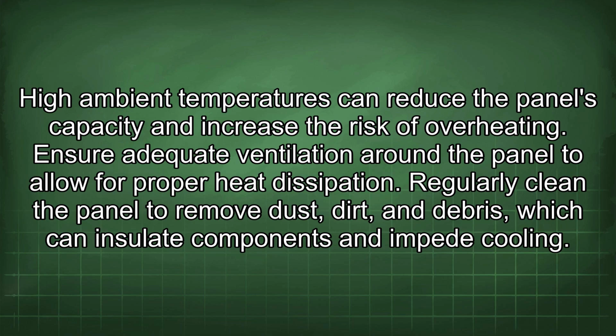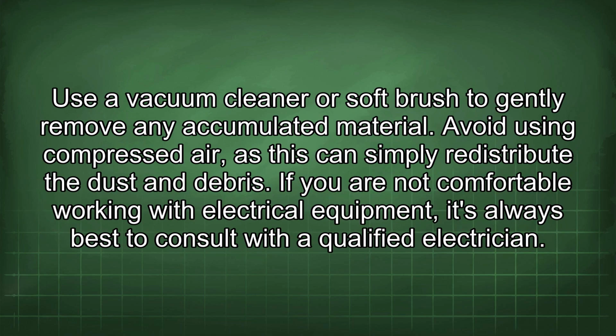Regularly clean the panel to remove dust, dirt, and debris, which can insulate components and impede cooling. Use a vacuum cleaner or soft brush to gently remove any accumulated material. Avoid using compressed air, as this can simply redistribute the dust and debris.